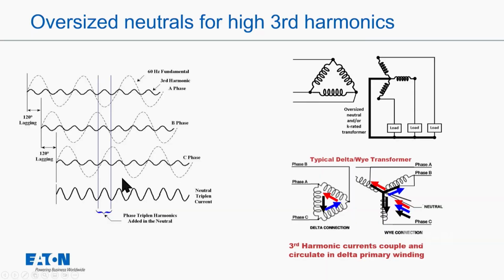So again, we've talked about this in many of the other videos, but the triplen harmonics, the third harmonics, add up on the neutral. So if that's the case, I could have excessive current on the neutral, and I could actually have a heating problem with it. In fact, that's why they doubled the neutral. It could theoretically get up to almost 180% of the normal current for the phase current. So if I had a 100 amp circuit on my phases, I could have about 180 amps on my neutral. So that's why they doubled the neutral. That's all related to third harmonics.